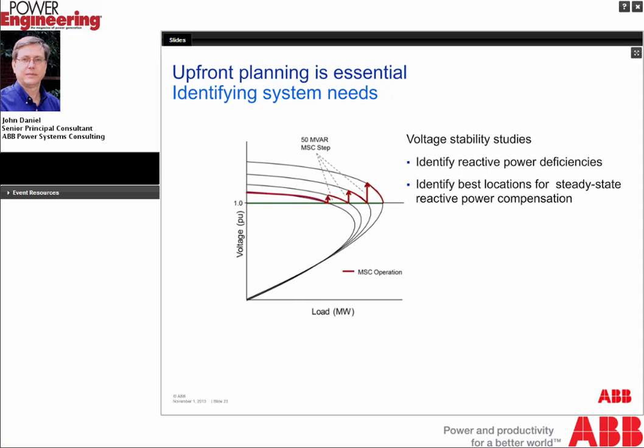The voltage stability studies can give you an idea of how close you are to a system collapse. Many of you may be familiar with the figure here. It's a traditional nose curve, and one way to address the loss of reactive power is to place capacitors out on the system. But as you place the capacitors out on the system, you tend to extend your nose curve and come closer to a voltage stability limit that may make your system actually a little more sensitive to changes in the system voltage. These stability studies can help identify where the reactive deficiencies are and identify the best locations for the steady state support.